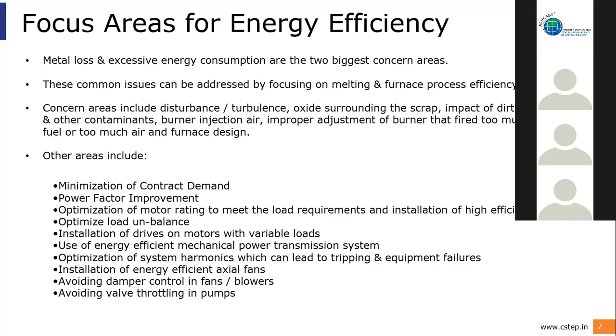Next comes the pumping. Now, pumping is a major area of concern, because today we have pumps which have efficiencies of around 80%. We can have an overall pump motor efficiency of around 67 to 70% operating efficiency. And in many MSME units, we found that the efficiency is as low as 35 to 40% for the pump motor set. And this is a huge saving opportunity. Next slide, please.